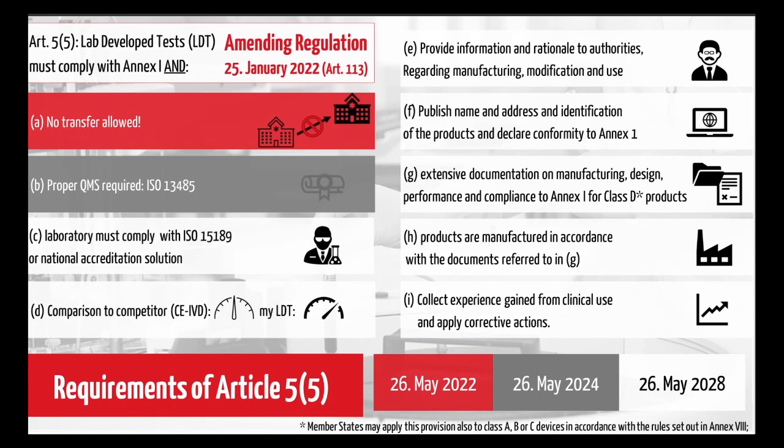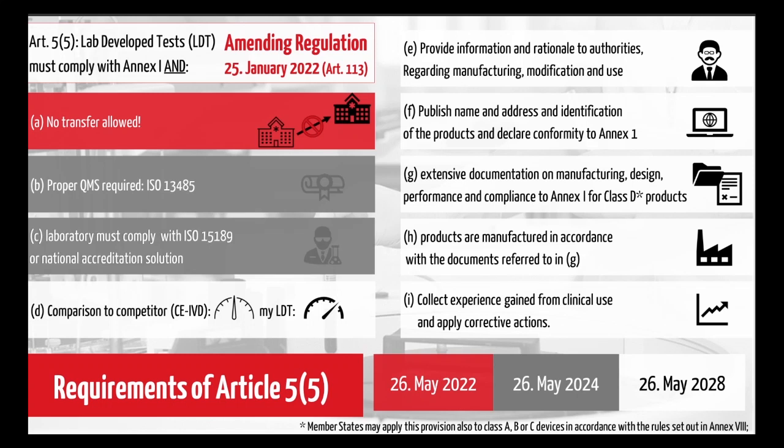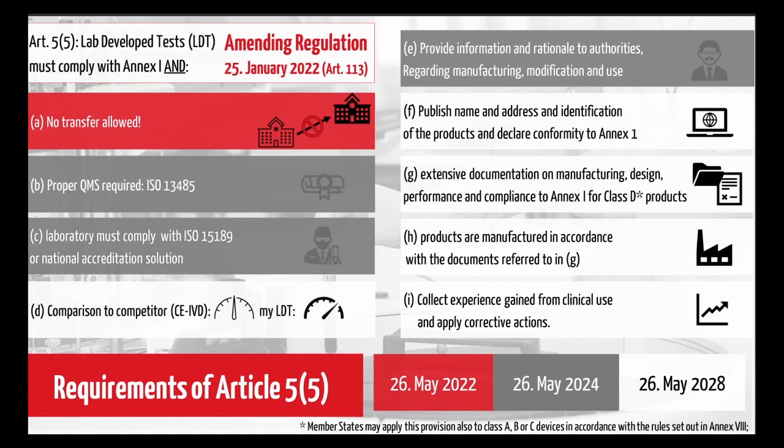That means a proper quality management system needs to be applied, which should cover aspects of ISO 13485, at least look into Chapter 7, product realization. And the laboratory must comply with the requirements of ISO 15189 or a respective national accreditation solution.